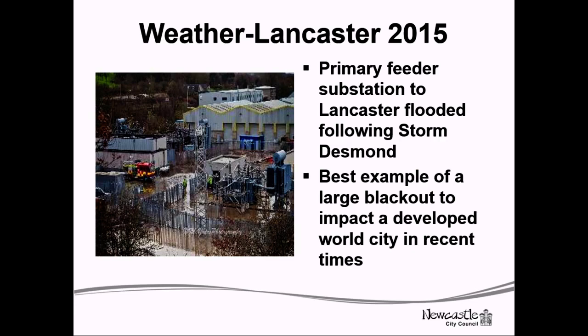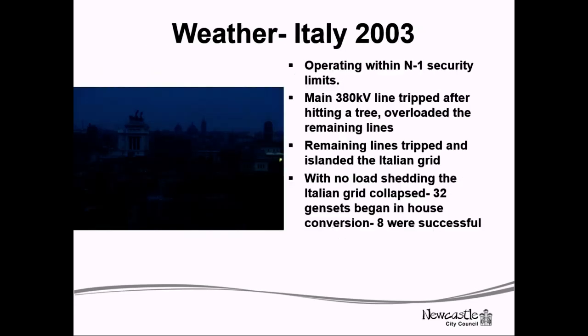Italy's blackout was partly caused by weather. The Italian grid in 2003 was operating within its N-1 security limit. N-1 is the principle that a grid can take one catastrophic event and still operate and continue to be secure and reliable. Essentially, Italy at the time, due to a price discrepancy, was importing electricity from the rest of the European network. So power was flowing over the Swiss border into northern Italy, and it had 2 380 kilovolt lines.